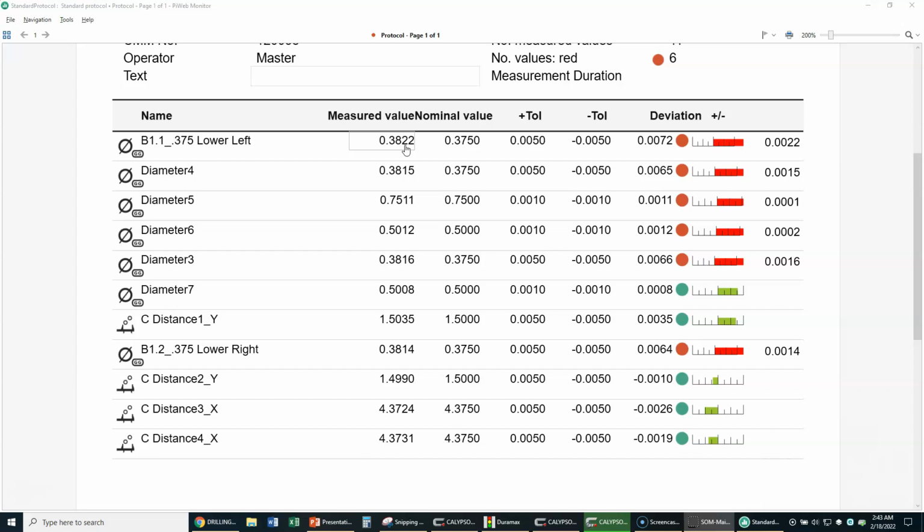You also want to make a note. I said this loosely. I said the dimensions you measure with calipers. What if you have a plus or minus 1,000th tolerance? We have a couple of those. Can you really use dial calipers to verify if you're within plus or minus 1? They're not really precise enough.